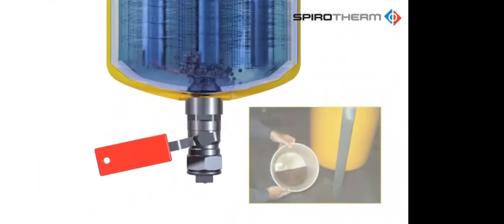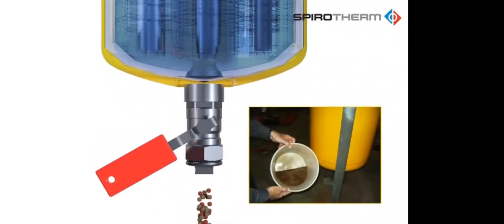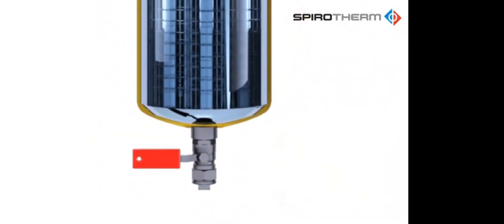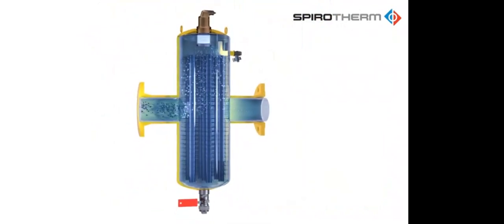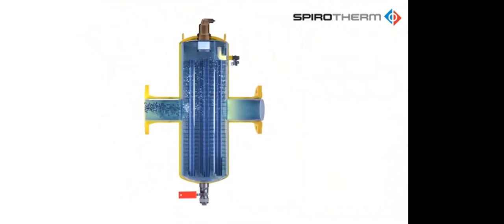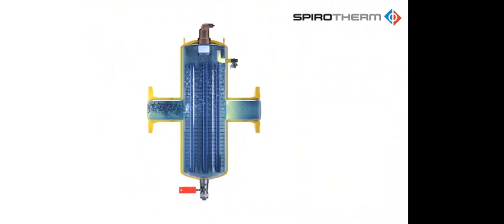Dirt can be flushed through the provided full port ball valve while the system remains fully operational. The large dirt collection chamber ensures infrequent flushing. Because the dirt is collected outside of the main flow path, blockages do not occur and Spirotrap pressure drop remains constant.